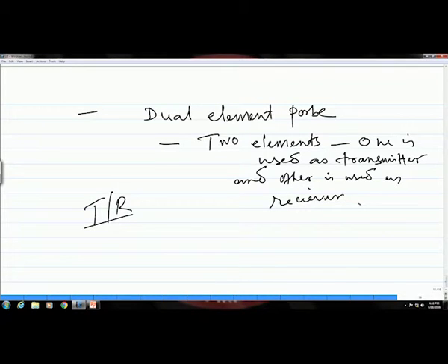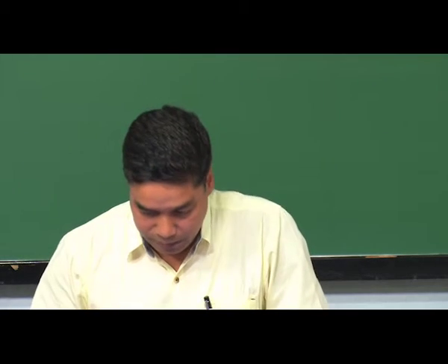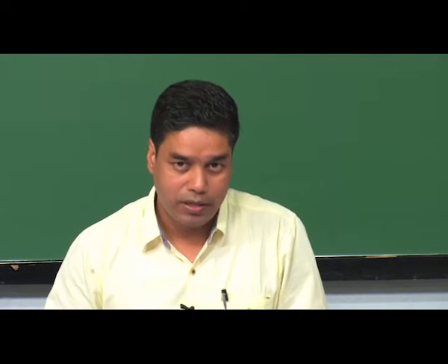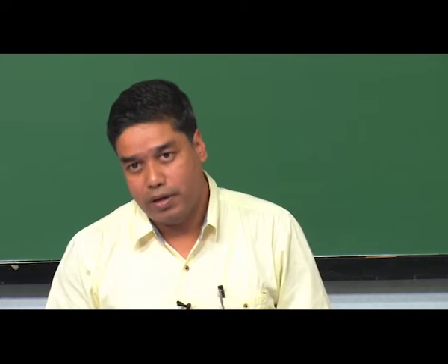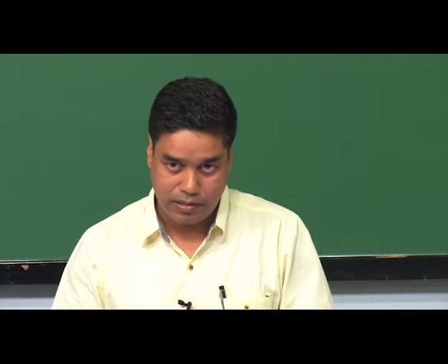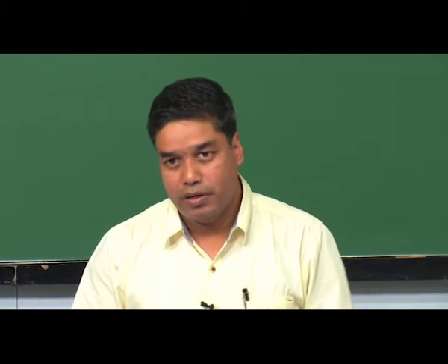Okay. So, in this case, since the same element is not transmitting and receiving, you do not have the problem that you have in a single element transducer. So, one probe will transmit the ultrasonic pulses into the sample, and the other one will receive.